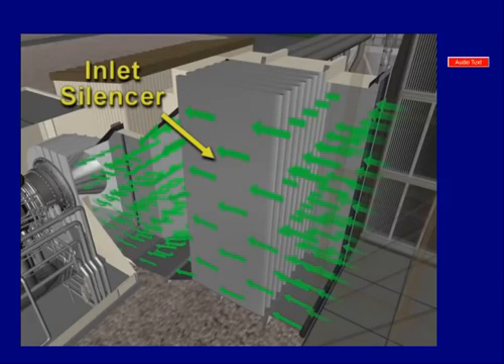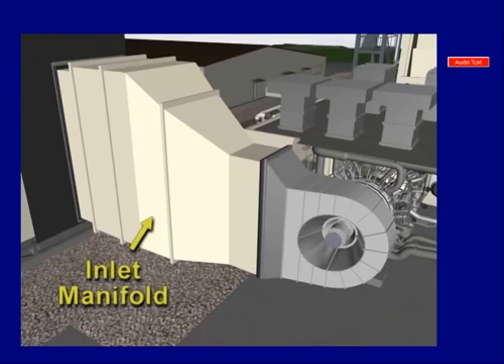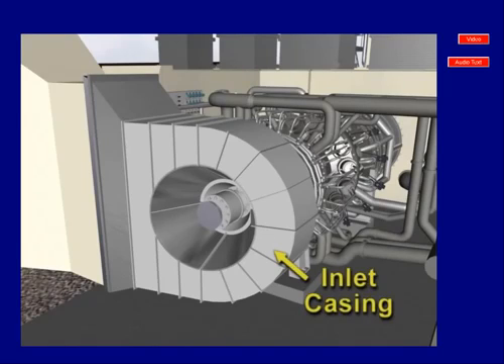Downstream of the mist eliminators, the air passes through the inlet silencer that is used to lessen the noise coming from the inlet air and the compressor inlet. The inlet manifold directs an efficient flow of air into the axial flow compressor inlet. The inlet casing provides a smooth transition flow of air into the axial compressor. Click on the video button to view an animation of the inlet air system.